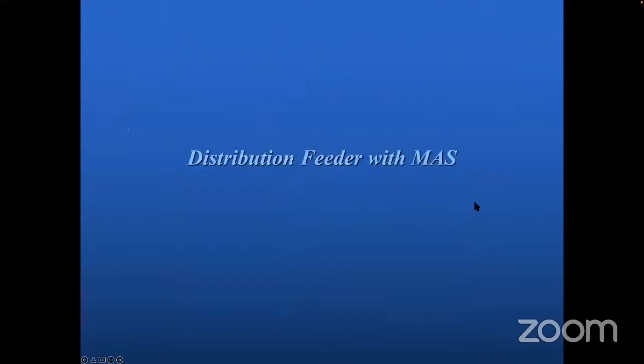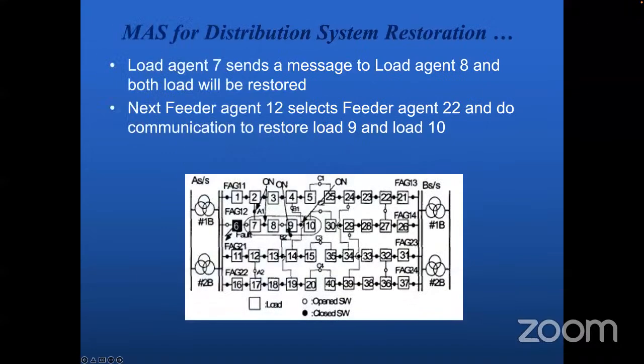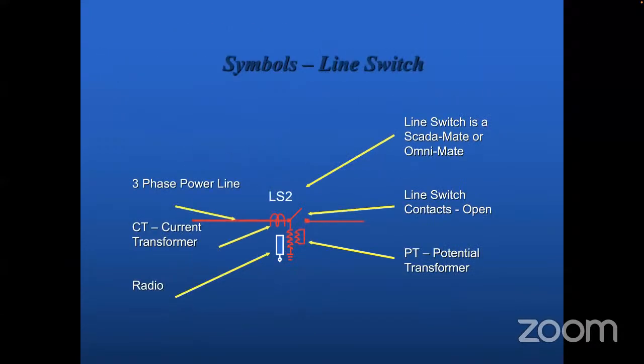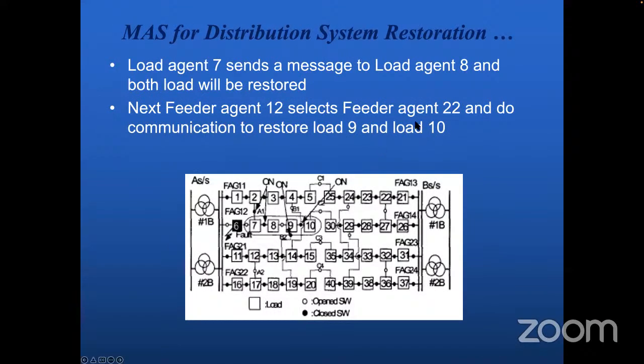If feeder agent 12 has the capacity, it will restore the load by closing that tie switch, closing this on switch, and loads 9 and 10 will be restored.